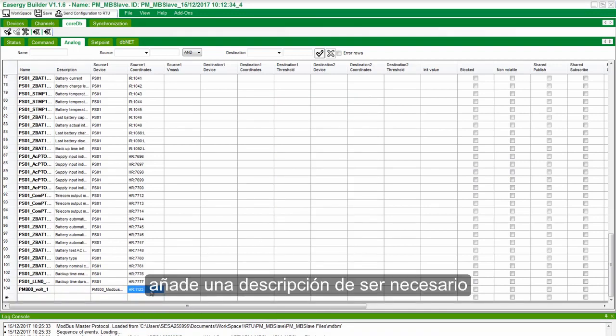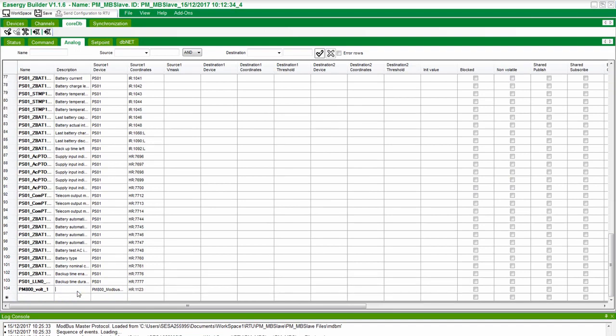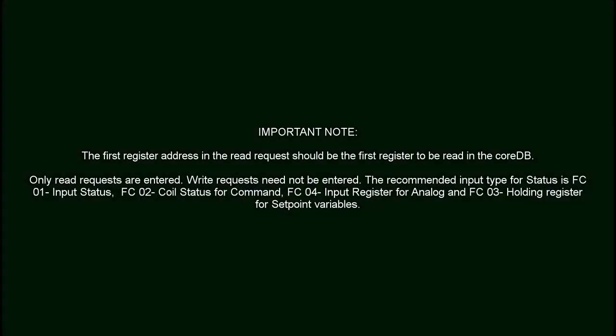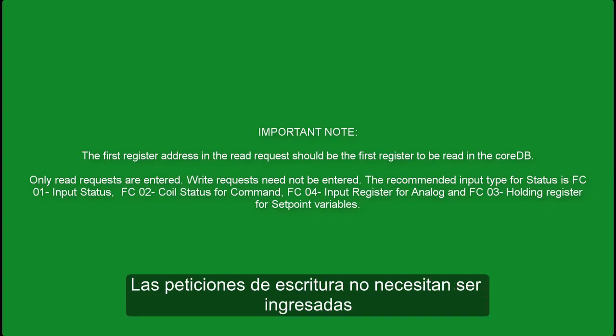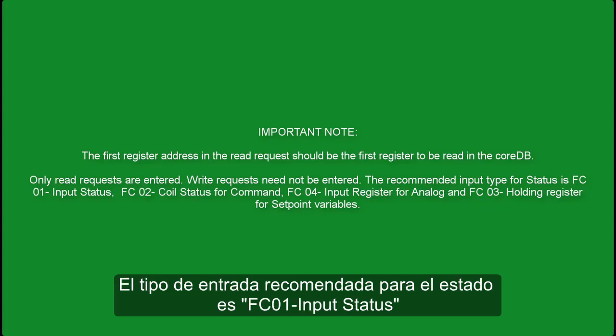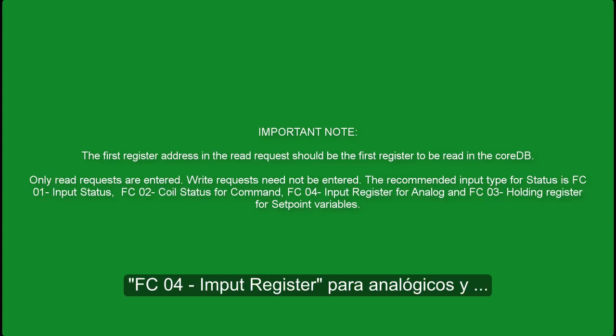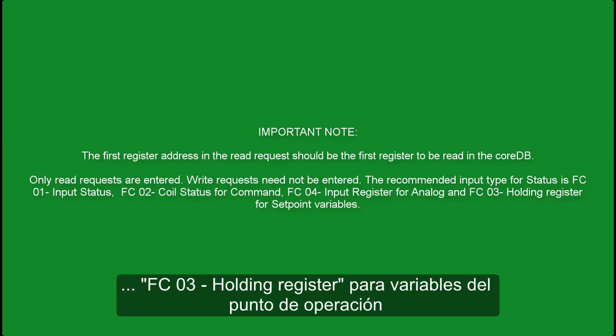Enter a description if necessary. The first register address in the read request should be the first register to be read in CoreDB. Only read requests are entered; write requests need not be entered. The recommended input type for status is FC01 Input Status, FC02 Coil Status for Command, FC04 Input Register for Analog, and FC03 Holding Register for Setpoint Variable.